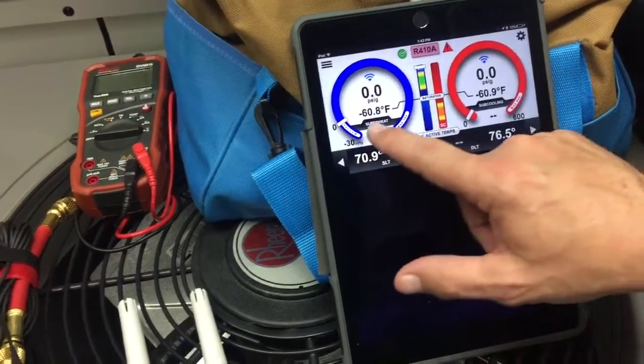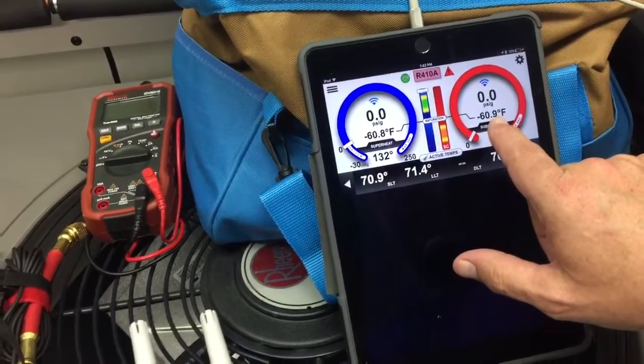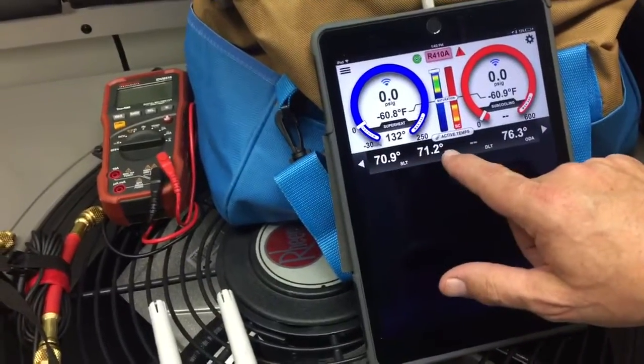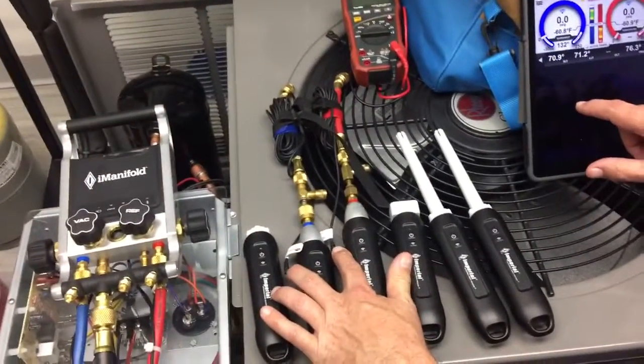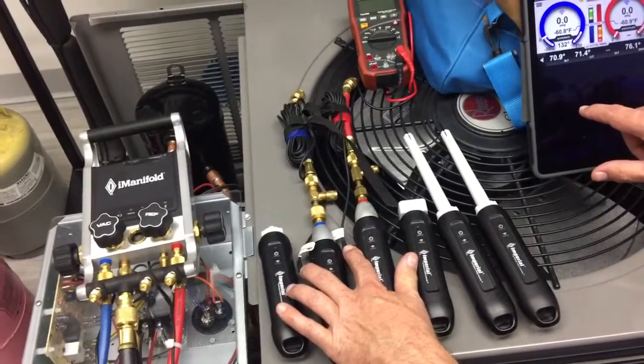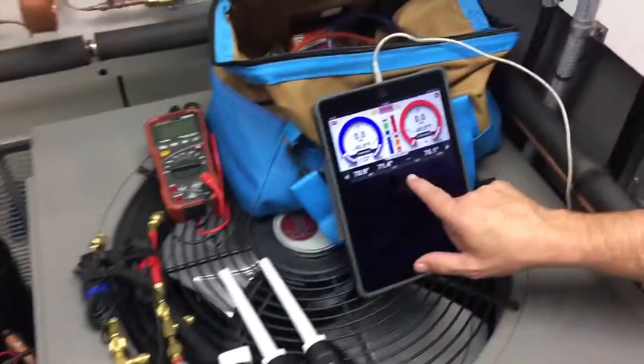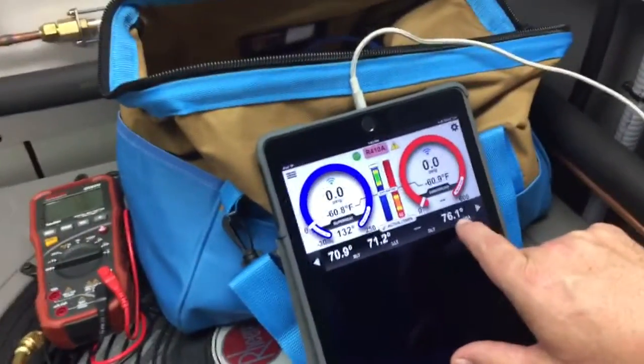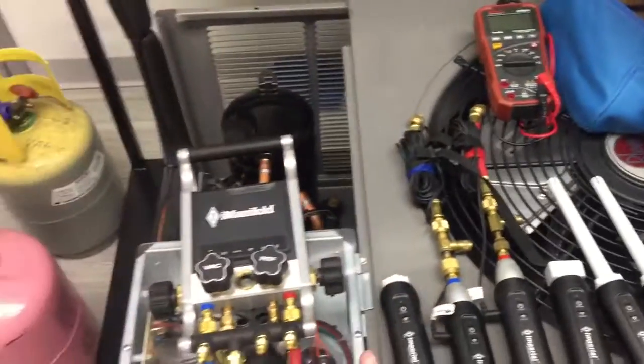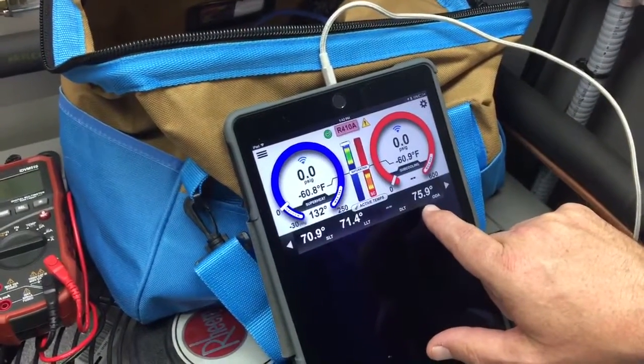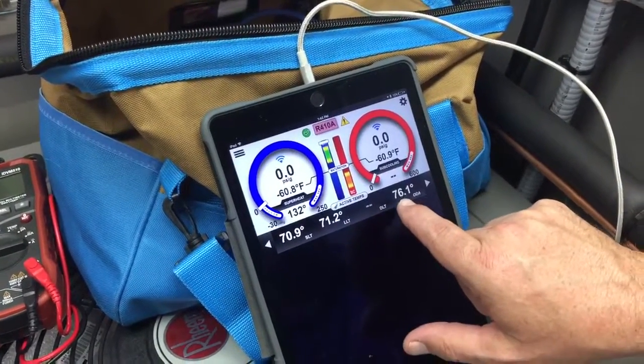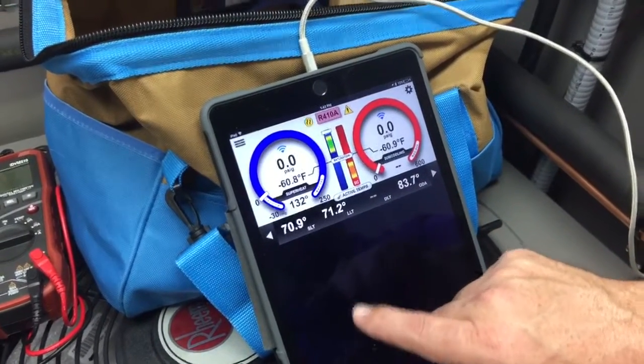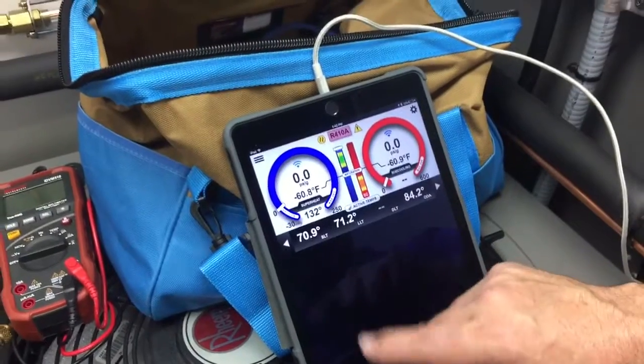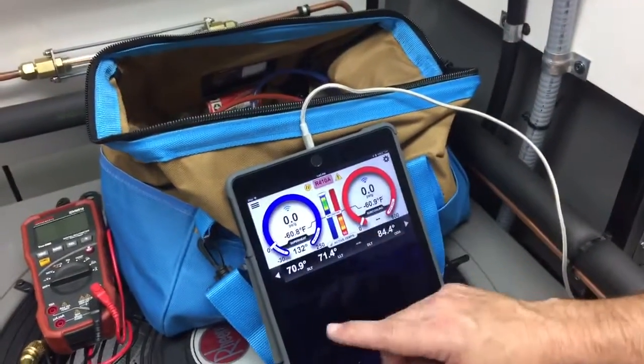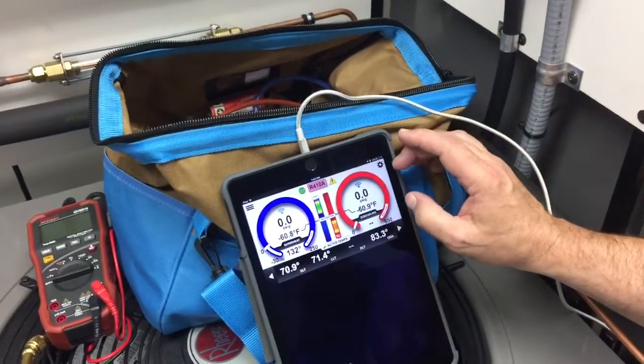So I just tap on that, and now I'm looking at the high and low pressure probes for circuit 2, and I'm reading the suction line and the liquid line off of these two T1 terminals on the high and low pressure probes respectively. I have a discharge line that's not mapped, and I have my outdoor air temperature, and this is the active outdoor air, which is coming off my iManifold right here. So if I grab this probe right here, you'll see that this outdoor air temperature will creep its way up. Some things like outdoor air, we don't read as fast as we read pressures and temperatures, because simply outdoor air doesn't change as quickly. So there might be a tiny delay in response on that, but that's perfectly normal, right? So this gives you a really good idea of how to do that.